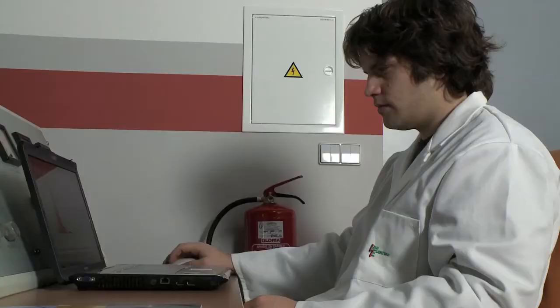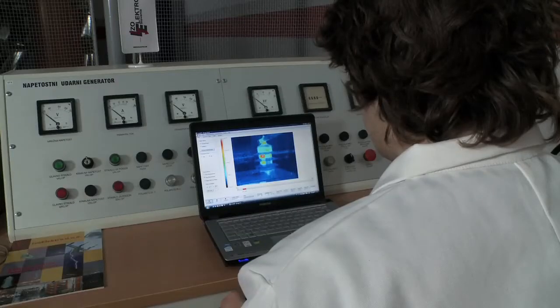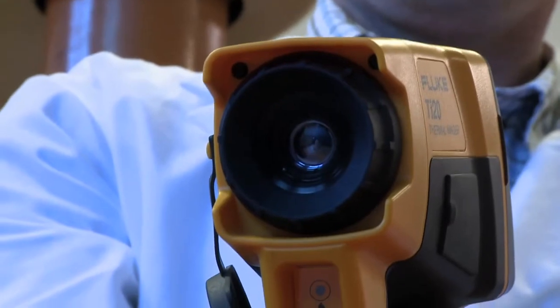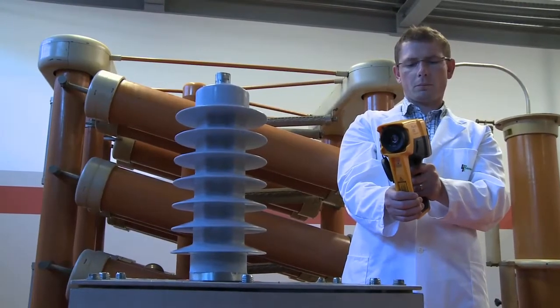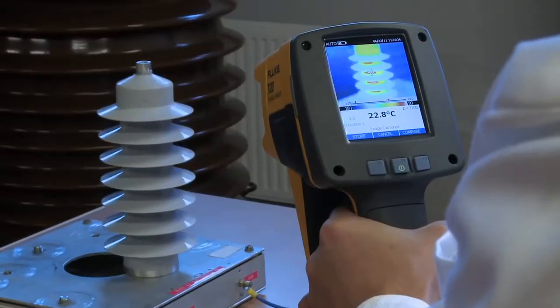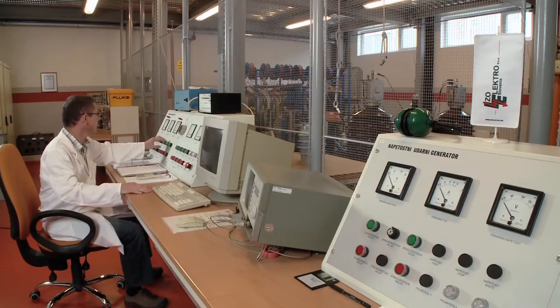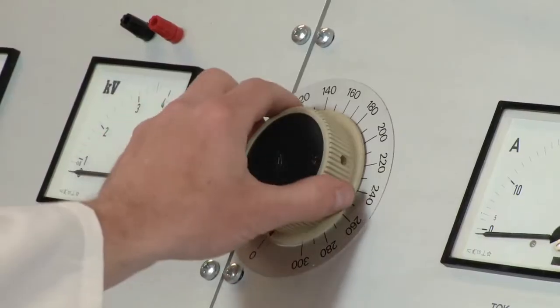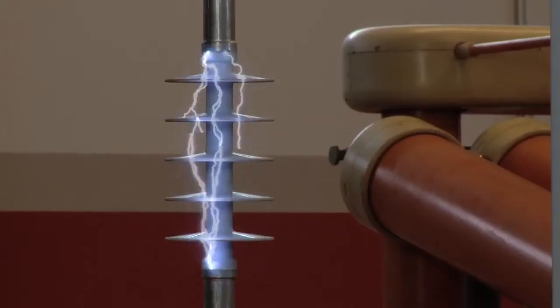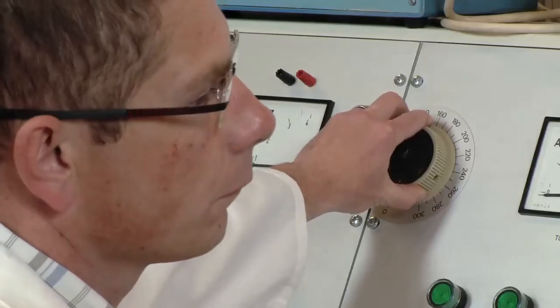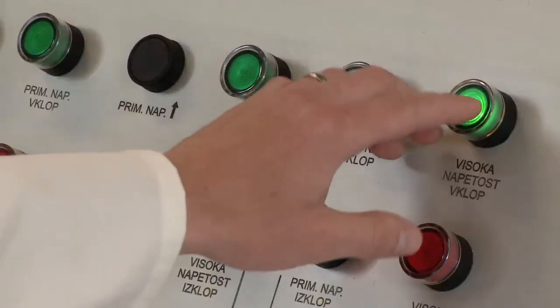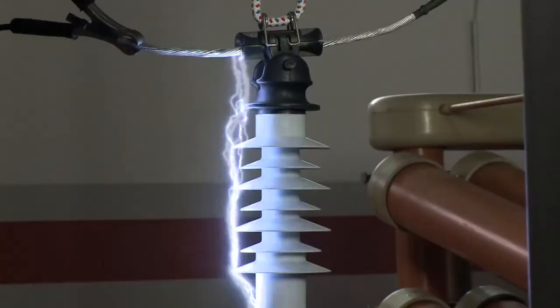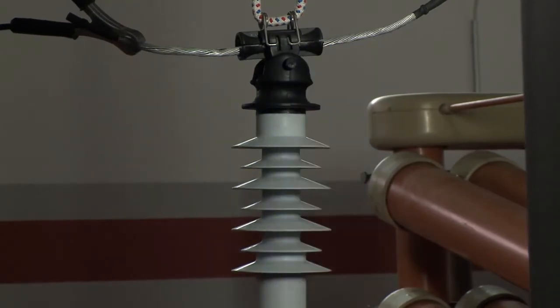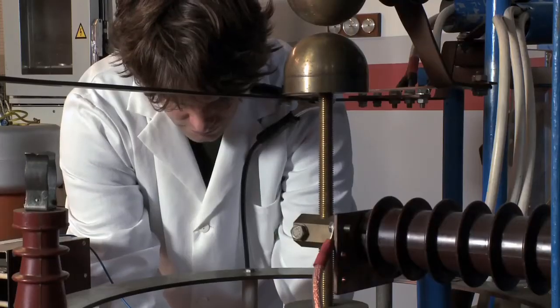We have our own high-voltage lab and constantly strive to improve it in accordance with standards. The lab allows us to run full tests on medium-voltage surge arrestors. The development and manufacturing requirements can be fully met by testing electric devices with alternating voltages of up to 220,000 volts and wave-shaped lightning impulse voltages of up to 1.2/50 microseconds up to 500,000 volts. Our most recent acquisition is the development of the testing environment for low-voltage surge arrestors with a peak value of lightning impulse current of 50,000 amps in the shape of 10/350 microseconds.